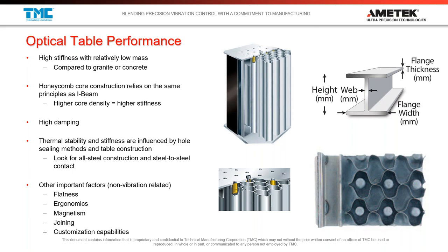When you compare this to other stiff objects that are used for this type of thing, like granite or concrete, it's very expensive to buy granite. It's very expensive to ship it. Concrete can't necessarily be made with the level of accuracy you could get by grinding a granite block. And the more mass you have, the more structural support you need in your building, but also the more isolation support you need to provide underneath it. You need isolation support that's proportionate to the mass of the system.